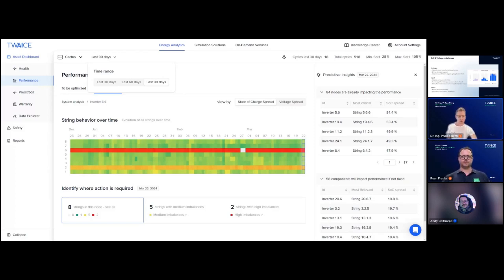Also, as we talked about the BMS SoC issues, as you can see here, this is the BMS SoC we get from the system, which says that you are only using the battery from 100 to 75% SoC. But if you look at the cell voltages, you actually see that we go below 3 volts, so we are actually pretty much discharged, which also gets reflected in the different TWAICE cell SoCs we calculate, where you see the maximum cell and the minimum cell being pretty far apart.